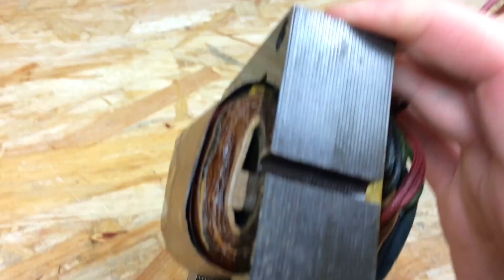For example, this particular transformer had small wooden wedges to help secure the bobbin to the laminations. That means we would have to drive out the wedges before attempting to remove the laminations.